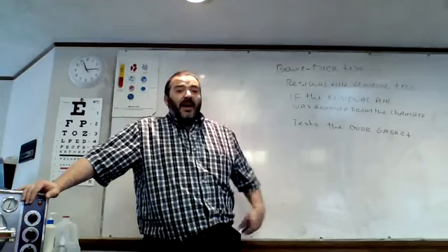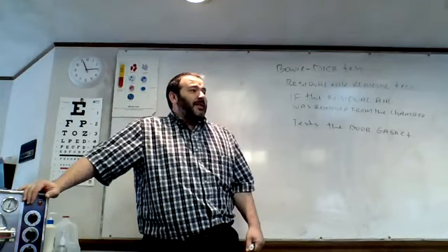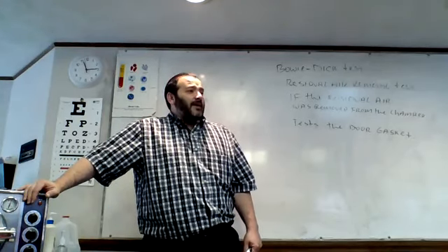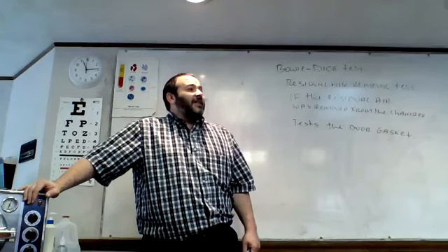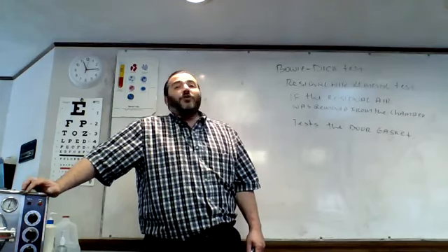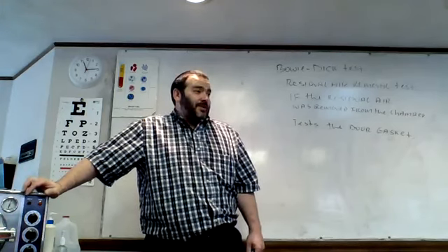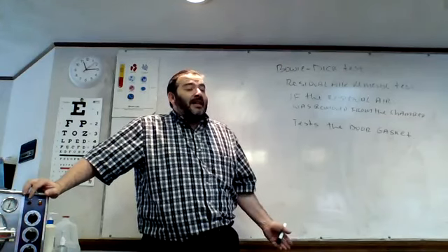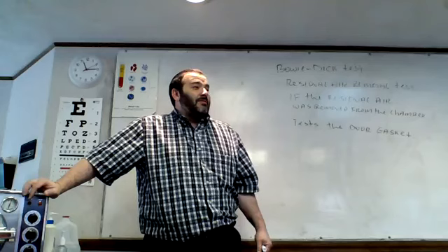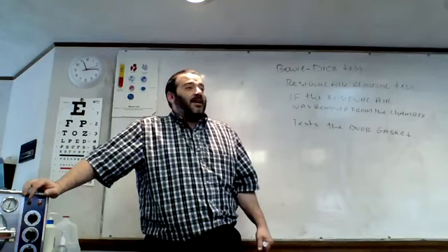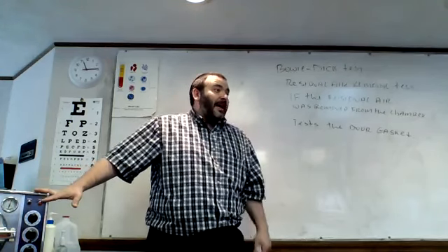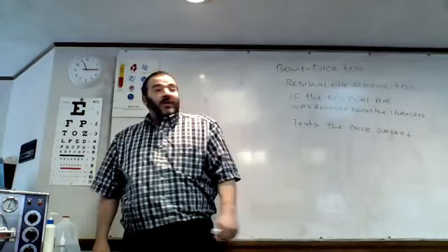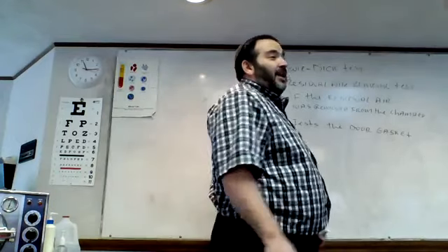If we don't create a vacuum, the Bowie Dick test or the residual test is going to fail. If it fails, the sterilizer is taken out of commission. You may not use it for sterilization purposes. It might work, but then again, it might not. You will never know. You will know when somebody gets sick, or more times than not, will die. You don't want that on your conscience now, do you?